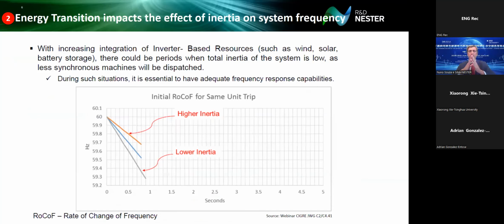This energy transition impacts the inertia on the system frequency. With the increase in integration of inverter-based resources from wind, solar, battery, and also EVs, there could be periods when the total inertia in the system is very low, with fewer synchronous machines being dispatched. So we see the rate of change of frequency increasing, going from 0.5 to 1, as we see here in the graph.